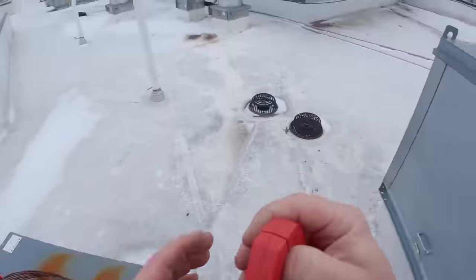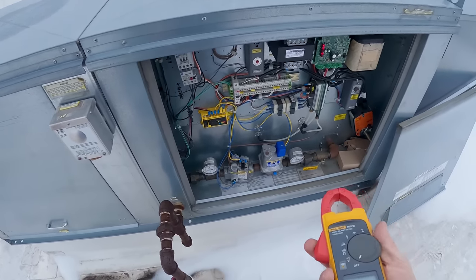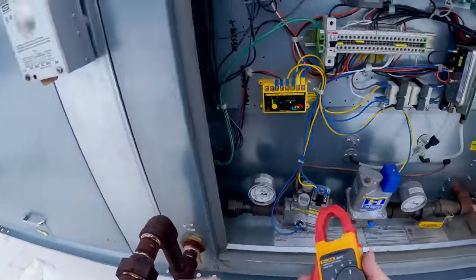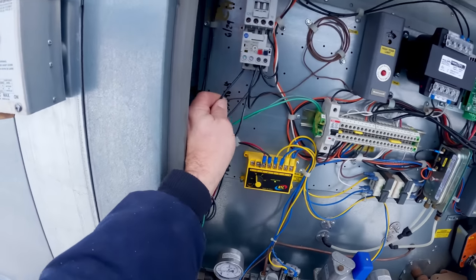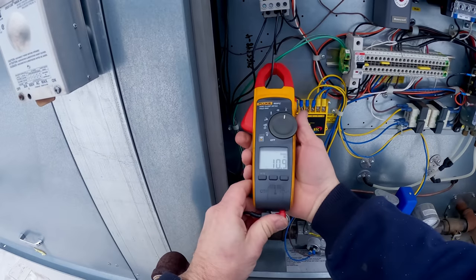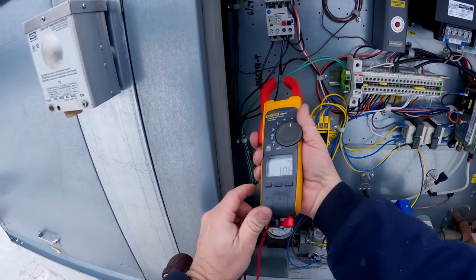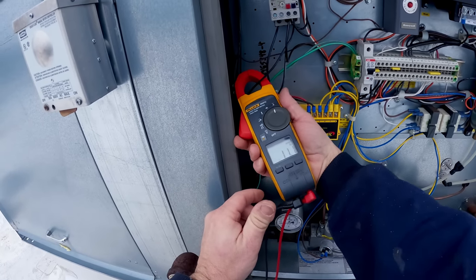See if we're over-amping, because that sounds like it's hauling the goods to market. Let's see what kind of amps we're getting here. Looks like three phase — that's kind of hanging in there, which makes me think it's been messed with recently. So there's 10.9, that looks like it's set pretty low, 10.6, 11.1.